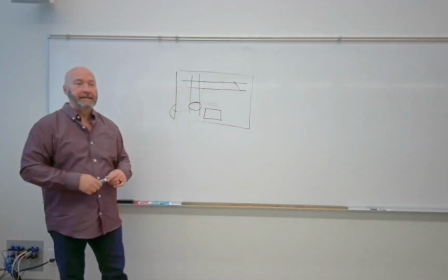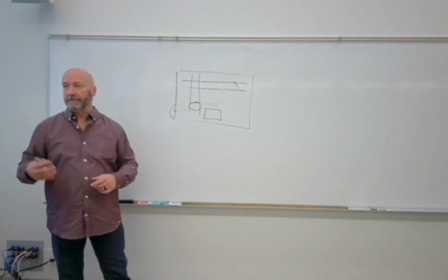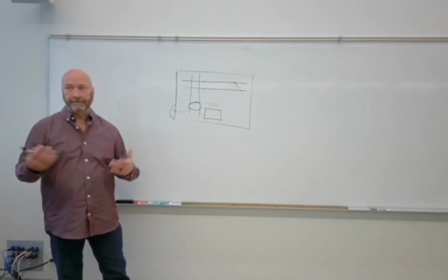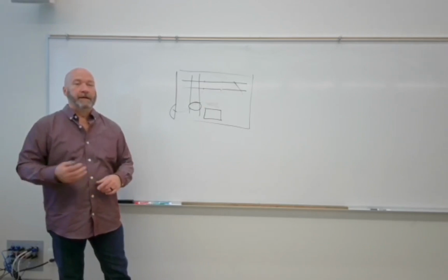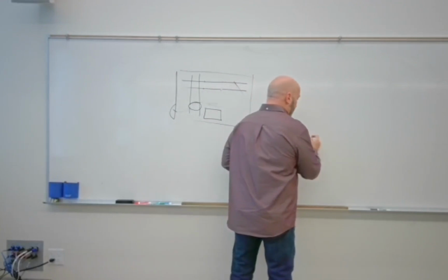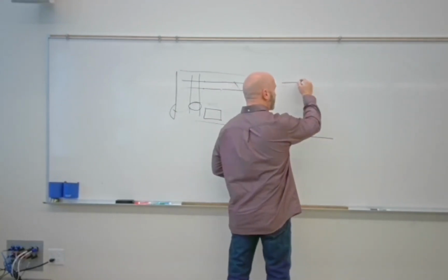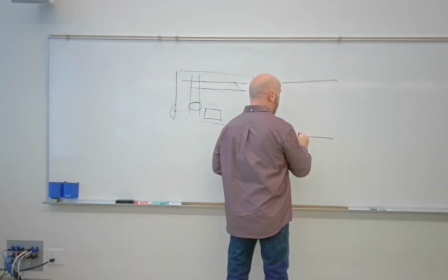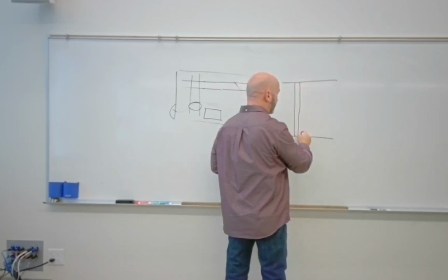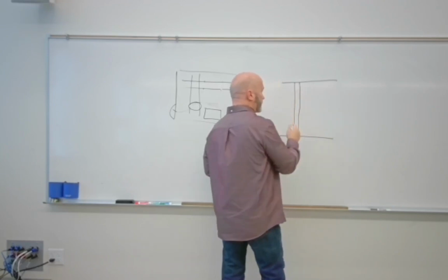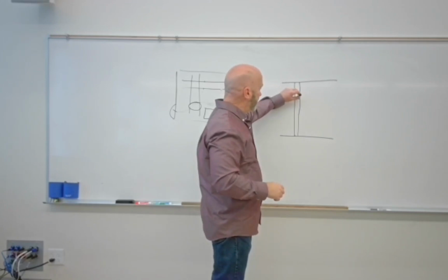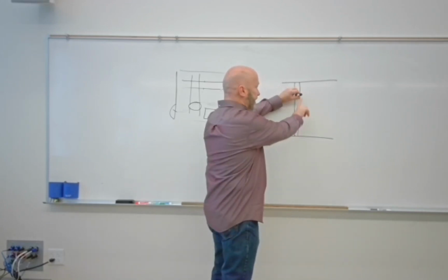So what they'll have is what they refer to as a ceiling to floor mounted system, and you might have seen these in your doctor's office. So if you go into just a doctor's office and you have an X-ray because you sprained your wrist or whatever, they take an X-ray, what you'll see is this system that runs on a track on the floor, and it's also got a track on the ceiling, and you've got this big arm or big stand that goes in between the two, and it can run up and down on those rails.